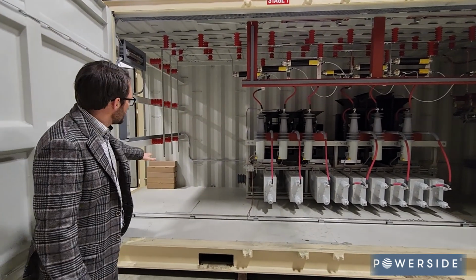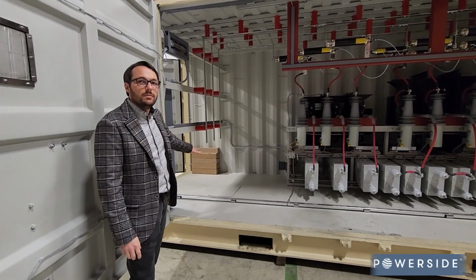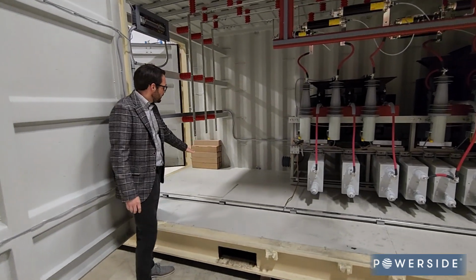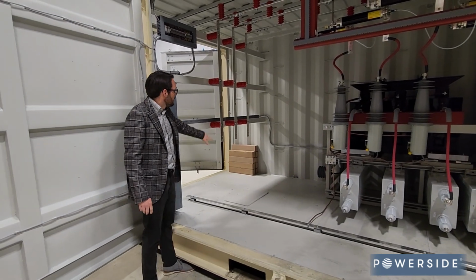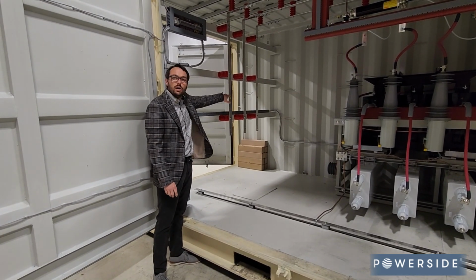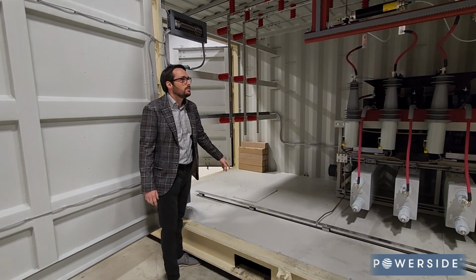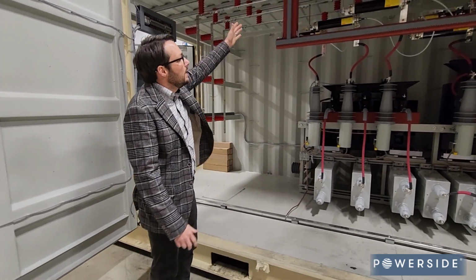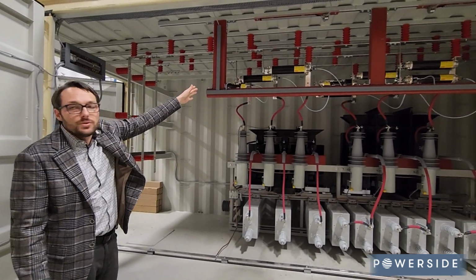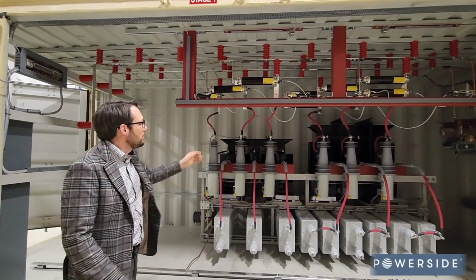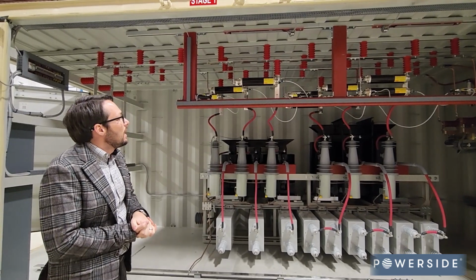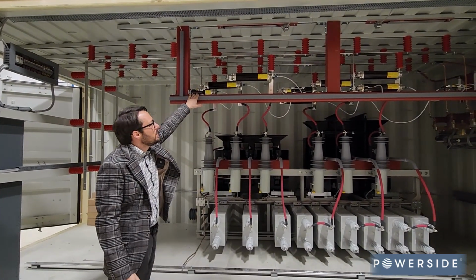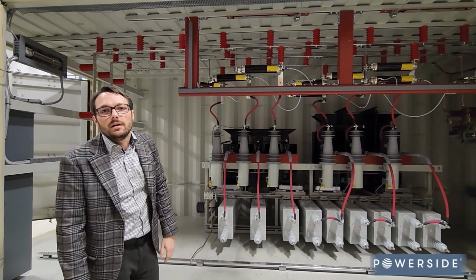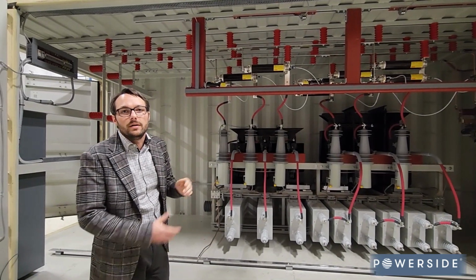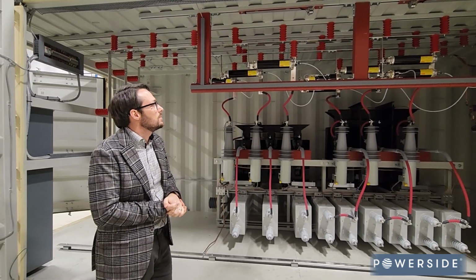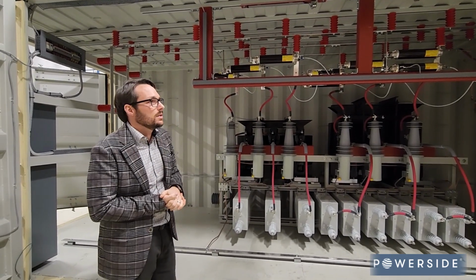The way it's configured, of course, is our incoming section here. It's going to be an underground feed. So the client will come in here with their incoming medium voltage cable, terminate on the bus. So we've got all our 3 phases and of course the ground. And then from there, we're feeding each of the stage sections. Fuses, of course, to protect each phase and on each stage. And those go to these micro switches here, which detect if a blown fuse indicator has occurred, or a blown fuse situation has occurred, which then comes back, of course, to the control.